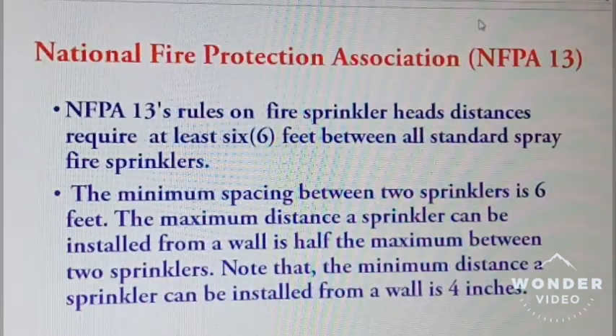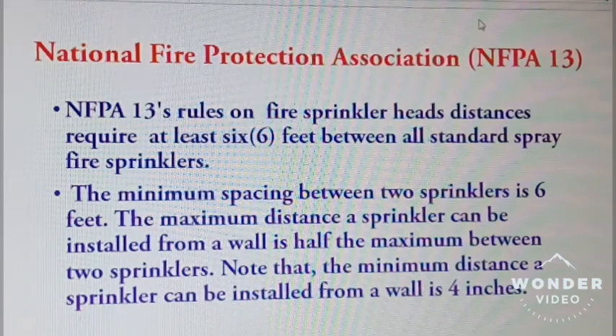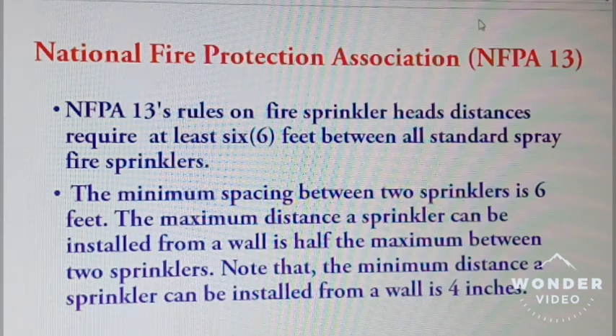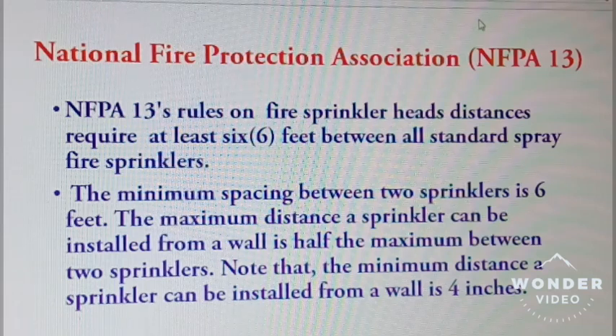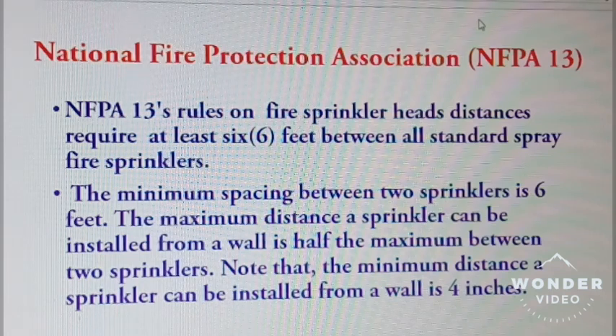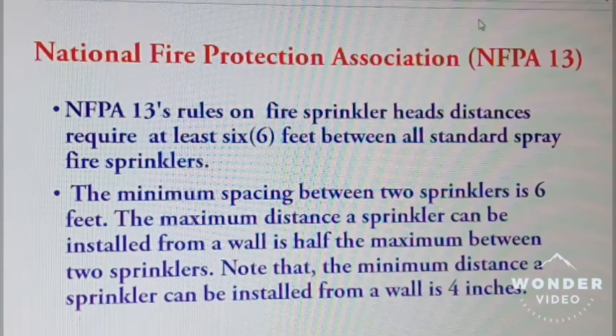National Fire Protection Association. NFPA 13 rules on fire sprinkler head distances require at least 6 feet between all standard fire sprinklers. The minimal spacing between two sprinklers is 6 feet. The maximum distance a sprinkler can be installed from a wall is half the maximum distance between two sprinklers. Note that the minimum distance a sprinkler can be installed from a wall is 4 inches.